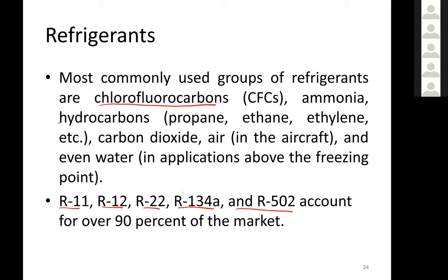Many of these refrigerants are now being replaced, for instance in domestic refrigerators. In the past, they used to use refrigerant 12. Now it's being converted, and we use R134A. R22, which was used for domestic uses, is basically being phased out, and R410A is being used in order to save the environment from harmful refrigerants.